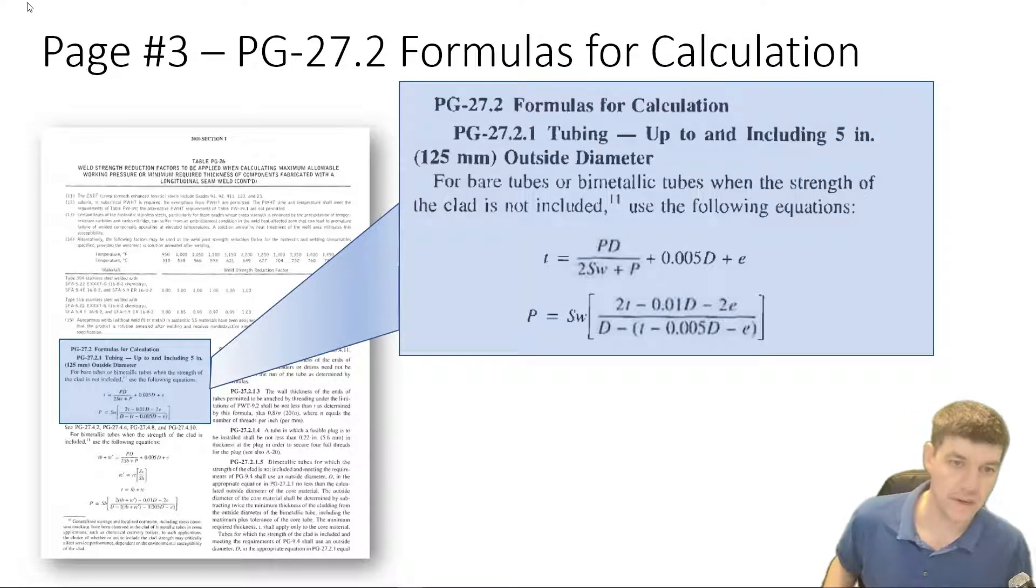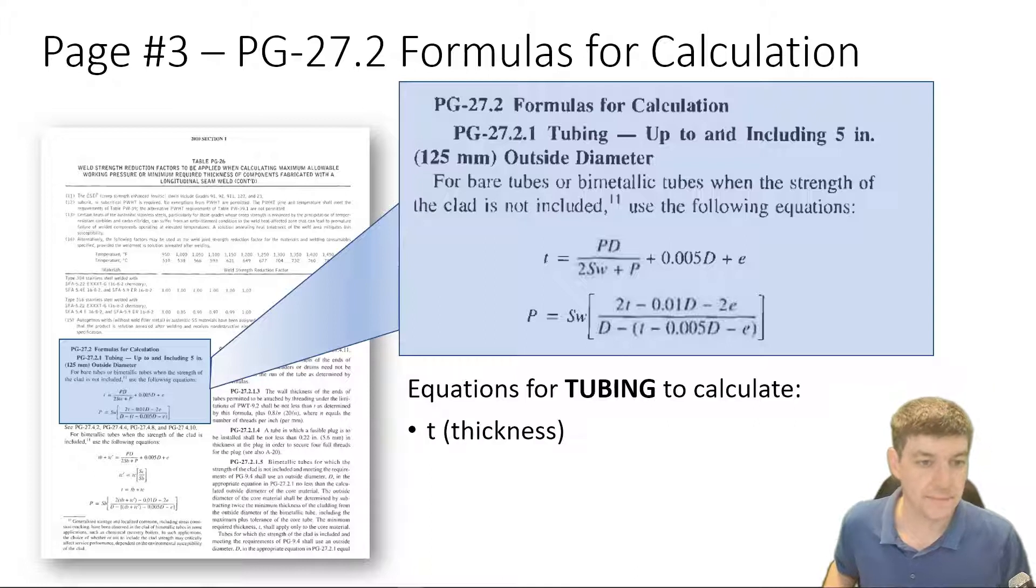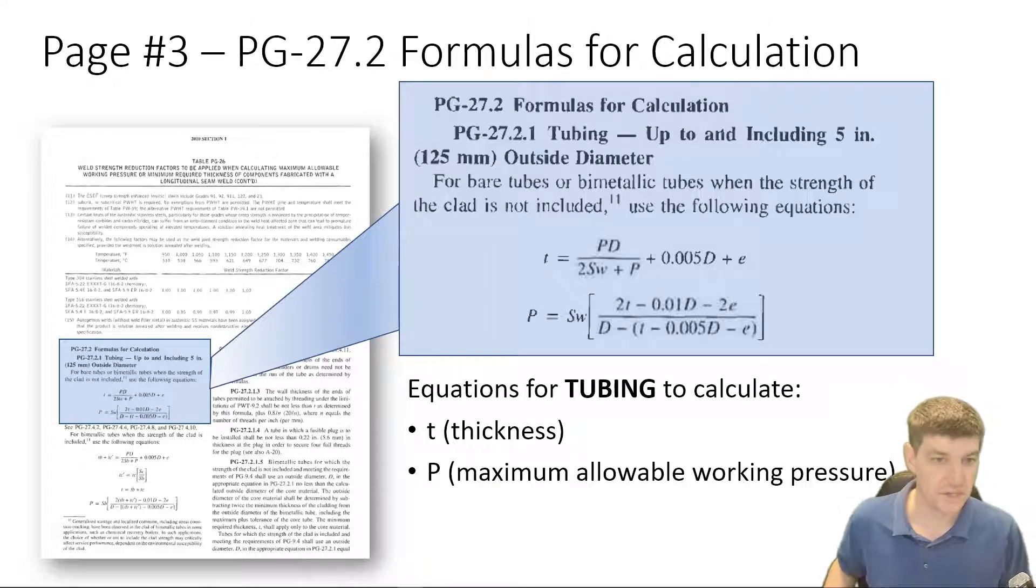These are for non-bimetallic tubes. They're for bare tubes. So we don't have any external strengthening to the tubes. And if they're just tubes, here's how we calculate them. We have two equations. One of them is for thickness, T. And then the other variation is if we want to calculate P, which is known as the MAWP, or the Maximum Allowable Working Pressure.